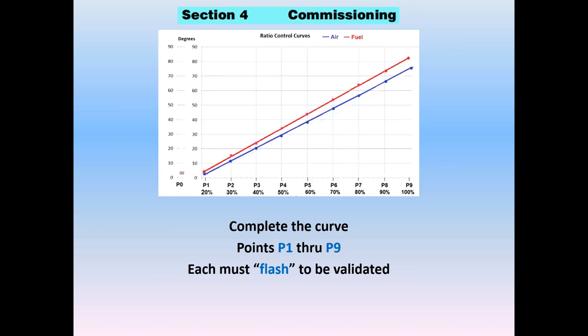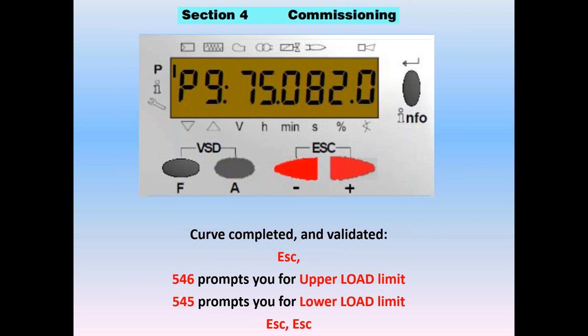Once the curve is complete — P1 through P9 — each point must flash to be validated. If you lose your flame, your load, or your burner turns down for any reason, all your data is retained, but points are not validated until they flash with that setting in there. You must flash on P8, P9, and every single point in your curve in either direction before you leave, so all points are valid combustion points.